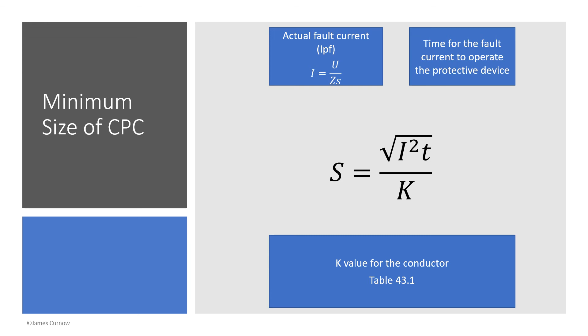The time for the fault current to operate the protective device is found in the time curve chart for that protective device. The K value for the conductor is found in table 43.1, bearing in mind the differences in temperatures for different cables could be 70 degrees or 90 degrees.